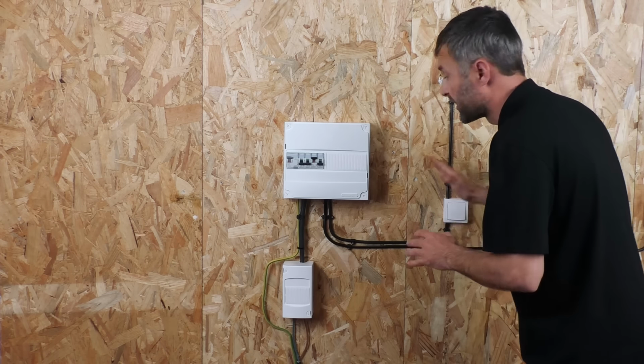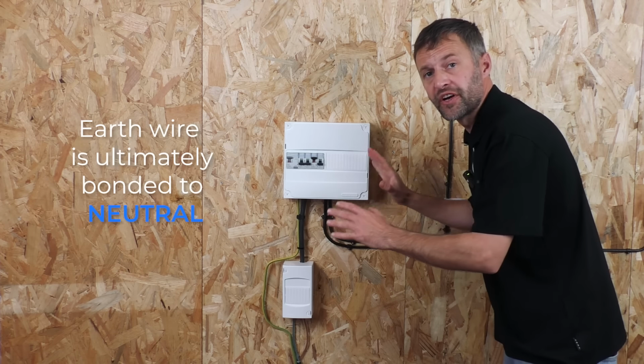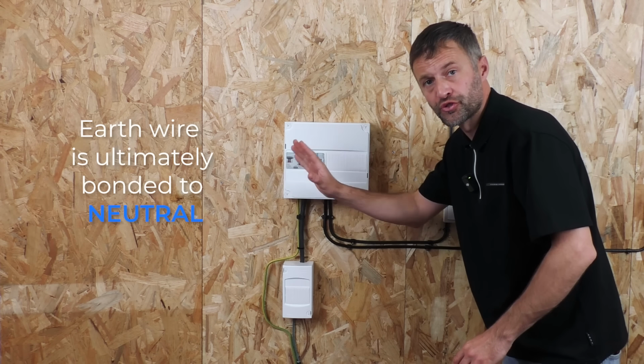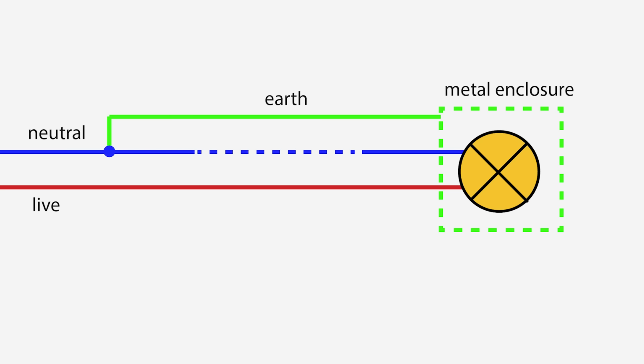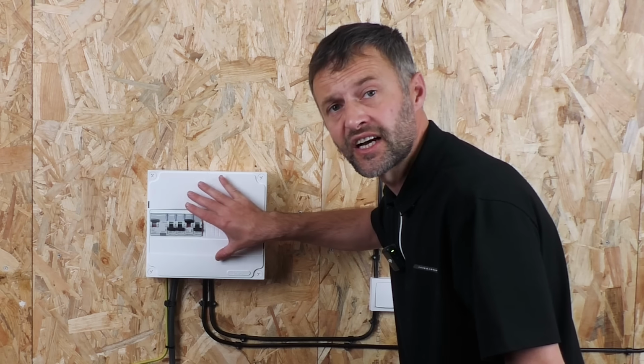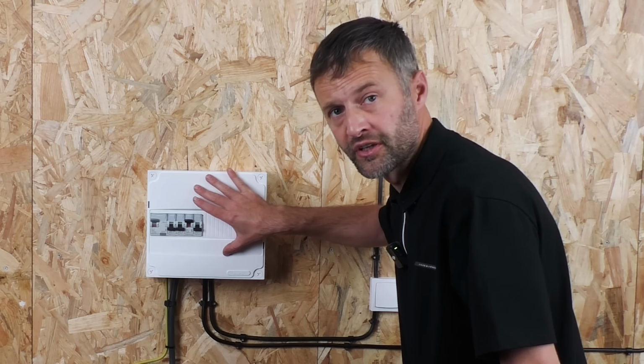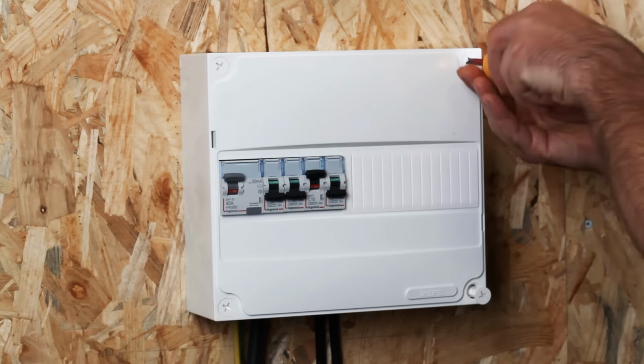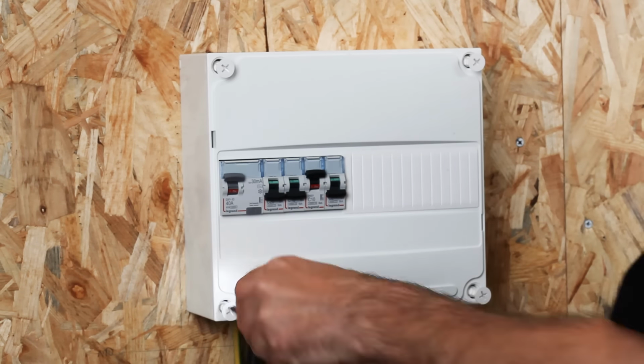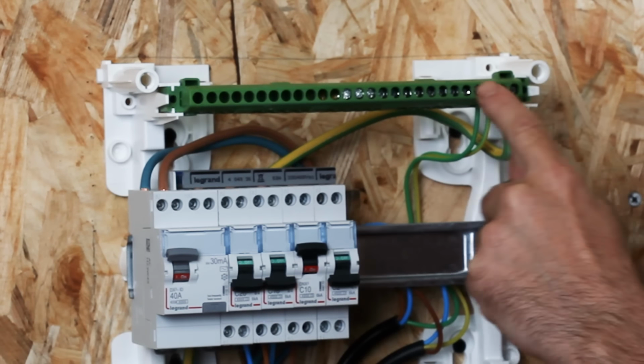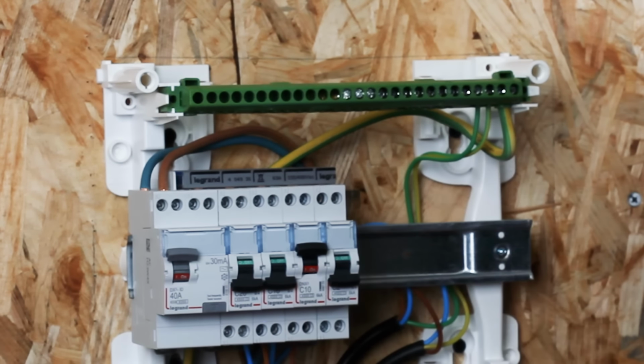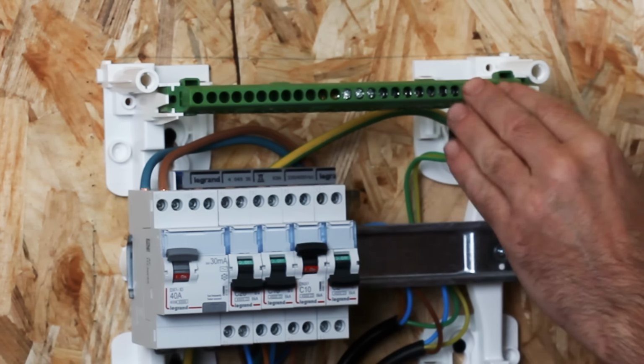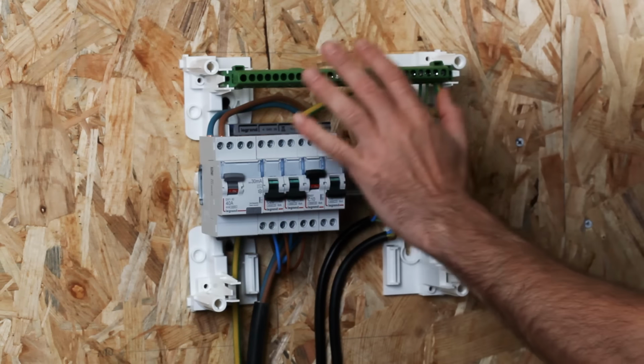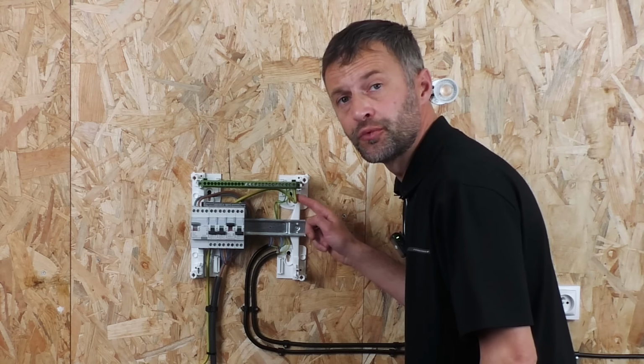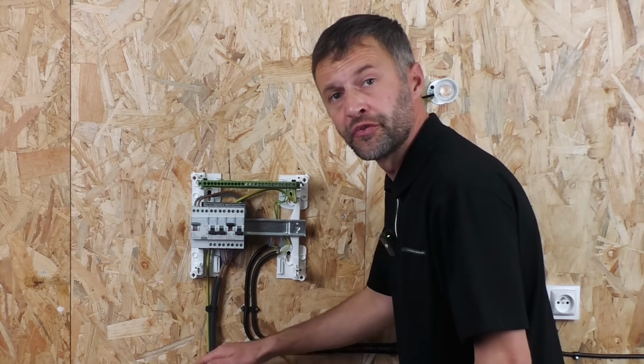The earth wire from there is connected to neutral, somewhere upstream, somewhere closer to the source, to the transformer. It can be connected inside the breaker panel. I'll open the breaker panel and show you. So this bus bar is where all the earth wires from your house wiring are connected, and this can be connected to neutral, but before the circuit breakers. In that case, you wouldn't need this thick earth wire going anywhere further.